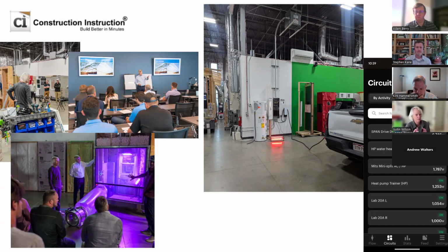Our firm does a lot of work with Canadian builders, and Canadian builders are electrifying at a high rate as well. It's interesting that we're looking at the term differently. In Winnipeg, Canada, which is far colder than pretty much anywhere here in Colorado, probably in line with Gunnison, but longer intensity and windier, they're looking less at backup and more at supplemental heat, or what is the balance when a heat pump starts to lose its capacity, so that I only make up that amount. So we're just supplementing that difference. Maybe, and the difference here is, maybe it's spun off of a hot water coil that's connected to something else.